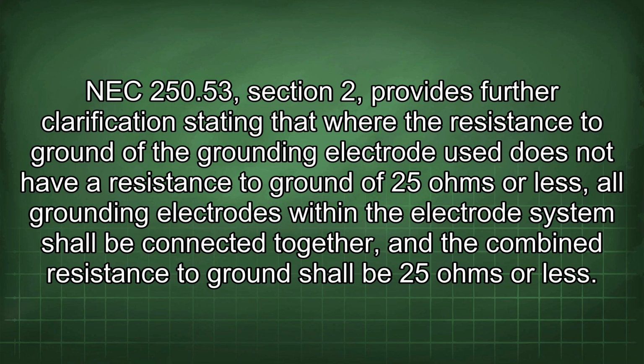NEC 250.53 Section 2 provides further clarification, stating that where the resistance to ground of the grounding electrode used does not have a resistance to ground of 25 ohms or less, all grounding electrodes within the electrode system shall be connected together, and the combined resistance to ground shall be 25 ohms or less.